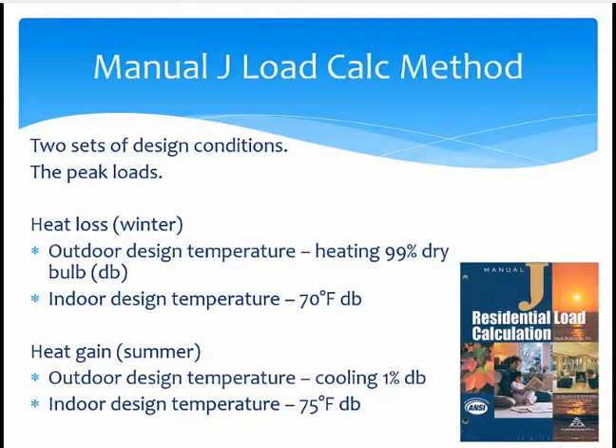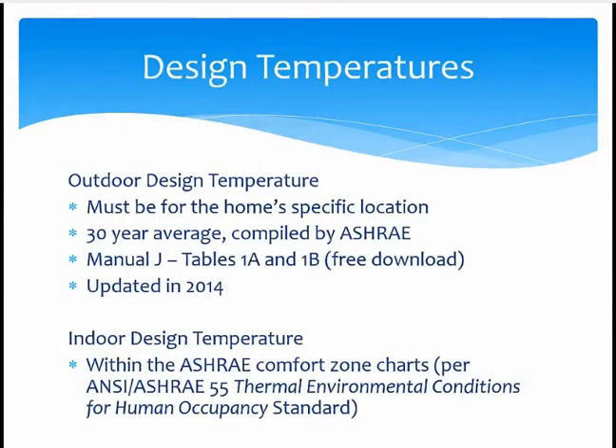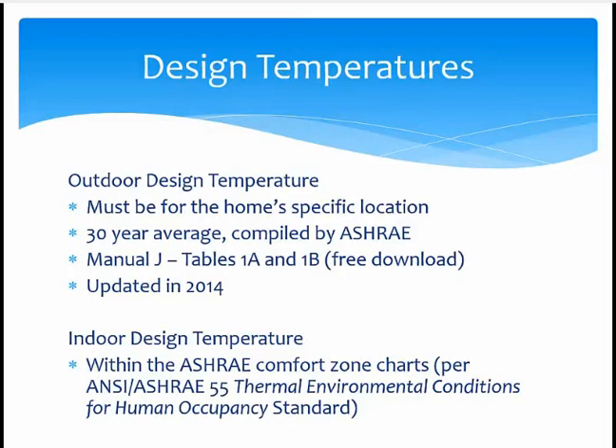So where do we get these design temperatures? The outdoor design temperature will be specific to the home's location — it's the 30-year average compiled by ASHRAE, and ACCA's Manual J has these temperatures in tables 1A and 1B. We also have these tables as a standalone document, offered for free download on our codes page. In the fall of 2014, we began updating these tables to comply with the latest ASHRAE data. The designer is required to use data for the city listed in the table closest to the home's location. The indoor design temperatures — 70°F for winter heating and 75°F for summer cooling — were chosen to comply with the comfort charts in ASHRAE Standard 55 on thermal environmental conditions for human occupancy.